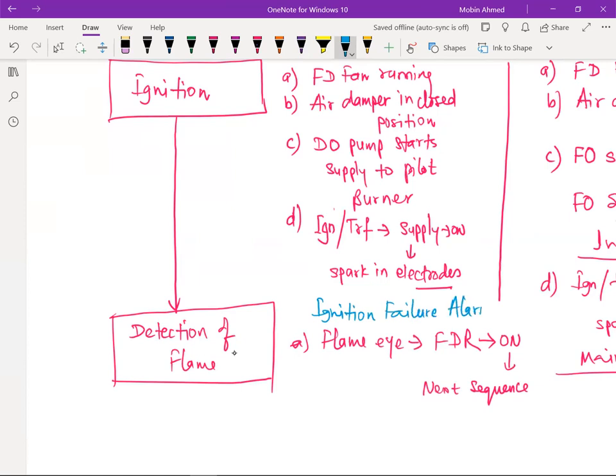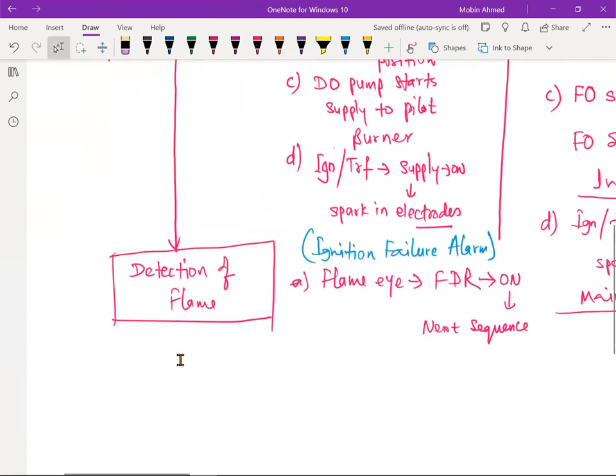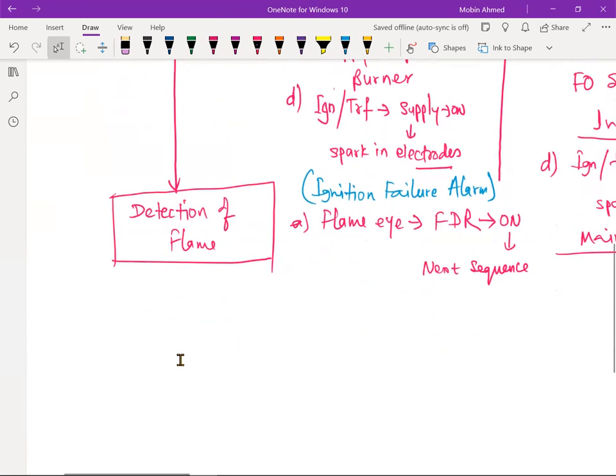This is the alarm. This is the first alarm you are going to get. Ignition failure alarm. Okay. Now, suppose detection of flame is already there, FDR is there. After the detection of flame, there will be the changeover. Okay, it is going to change over.